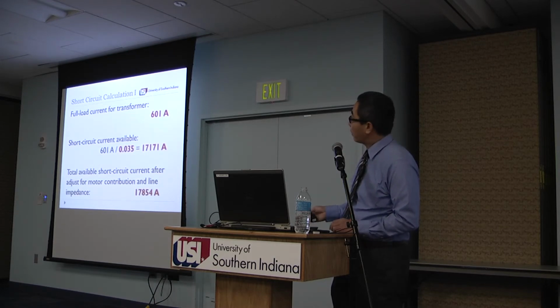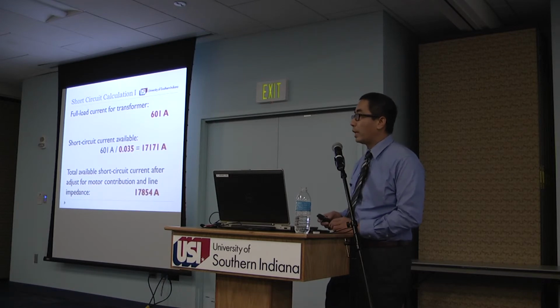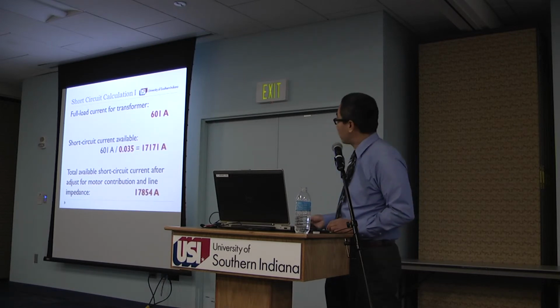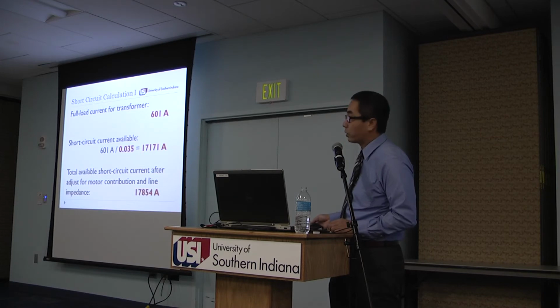And for our project, we do it just for one transformer. That's the rated current capacity of that transformer, 600 amp. You divide it by the impedance of the transformer. That gives you the available short circuit current at the transformer itself. That's 17,000 amp. So you can tell the difference.